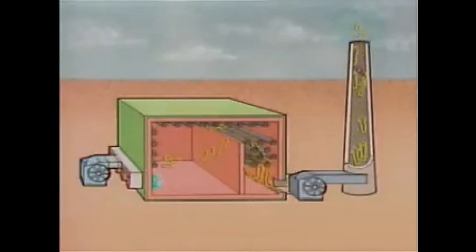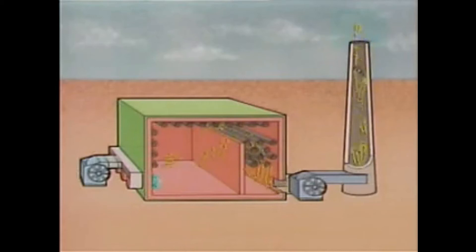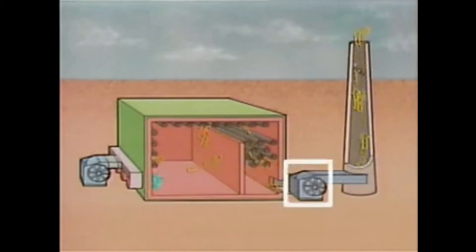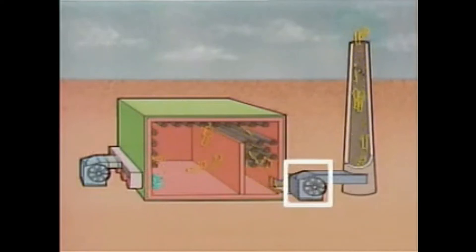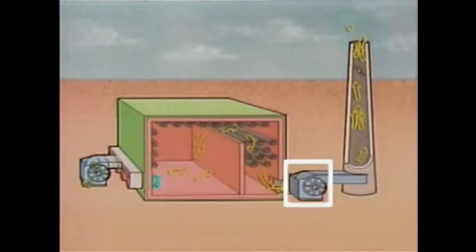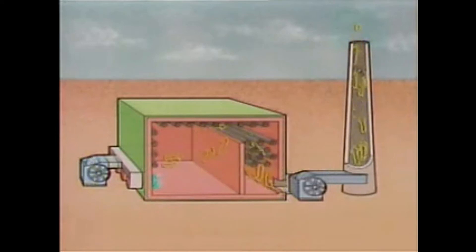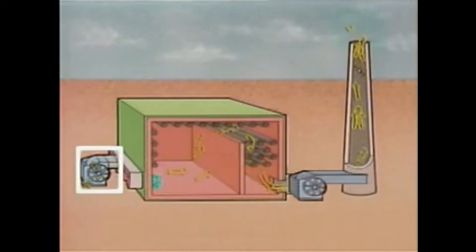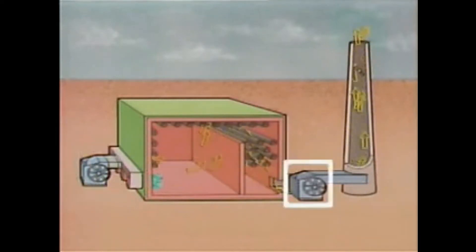Another type of furnace is a balanced draft furnace. A balanced draft furnace is similar to a force draft furnace, but it has another fan in addition to the force draft fan. The second fan is called an induced draft fan, and it is located in the flow path of the combustion gases between the furnace and the stack. So in a balanced draft furnace, one fan provides air for the burners and the other fan removes the combustion gases.